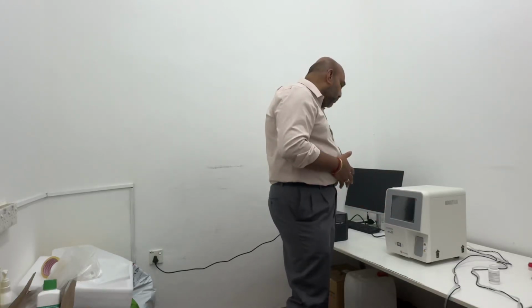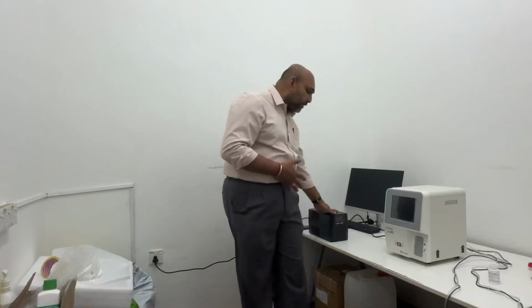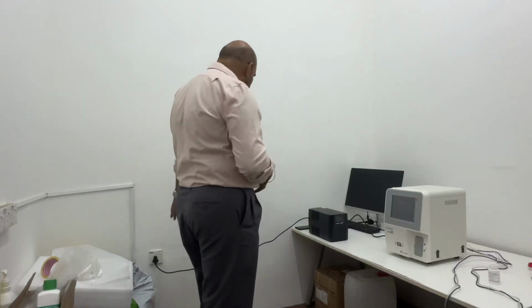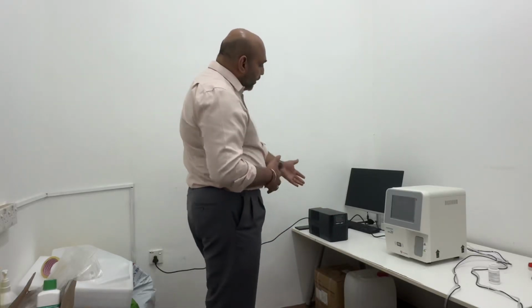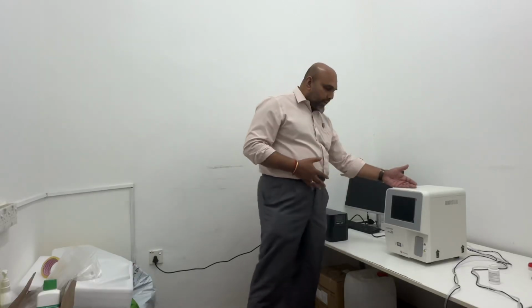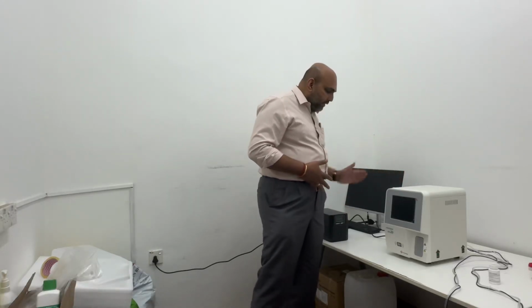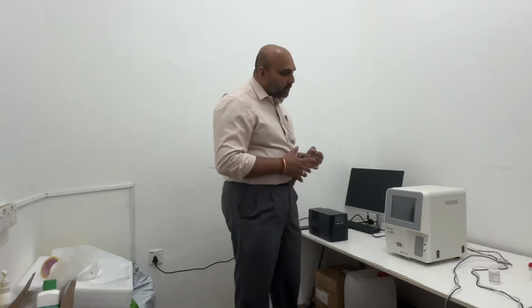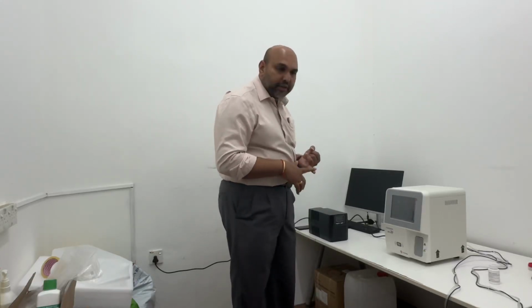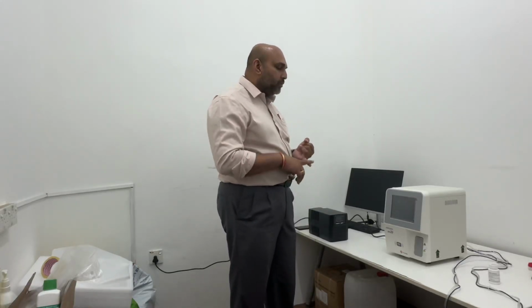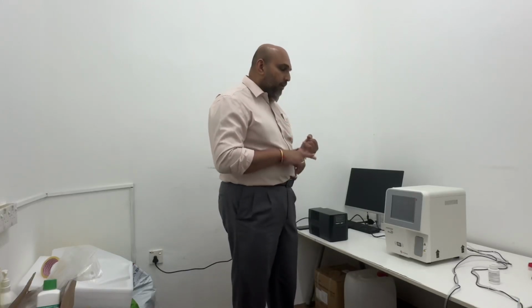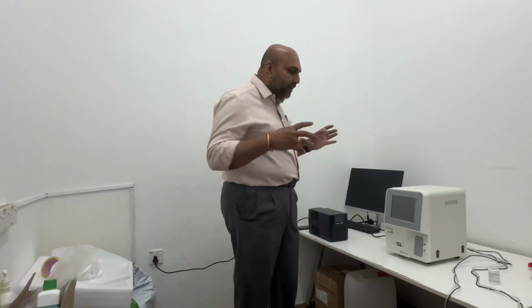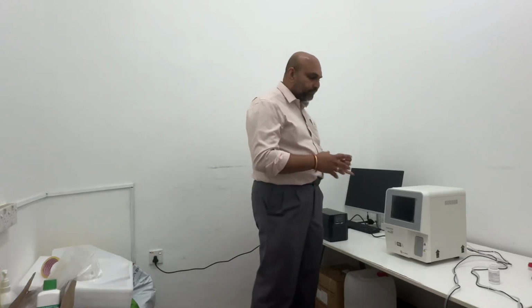So when using a UPS, it stabilizes the voltage from the main supply before it goes to the analyzer. This way, the machine can give you a perfect result, especially for the parameter hemoglobin, HGB, because HGB has a direct connection with the voltage.